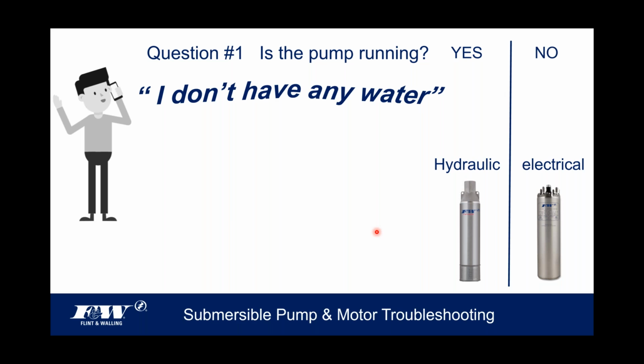If the customer responds back and says, no, the pump is not running, now let's think about this for a second. The pump is not running, which might be a good reason why they don't have any water, right? But what runs the pump? Well, it's the motor, right? It's the motor side of that. And so by asking that very fundamental question, and I'm not saying I'm going to stay on this path, it gets me headed down a path where I'm going to try to determine whether this is a motor issue or whether it's a pump end issue.